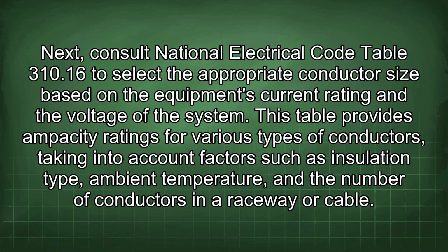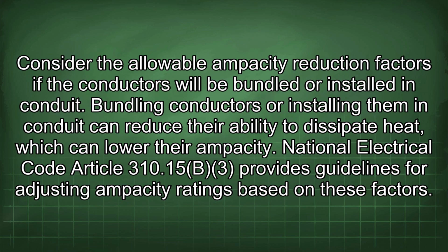Next, consult National Electrical Code Table 310.16 to select the appropriate conductor size based on the equipment's current rating and the voltage of the system. This table provides ampacity ratings for various types of conductors, taking into account factors such as insulation type, ambient temperature, and the number of conductors in a raceway or cable. Consider the allowable ampacity reduction factors if the conductors will be bundled or installed in conduit. Bundling conductors or installing them in conduit can reduce their ability to dissipate heat, which can lower their ampacity. National Electrical Code Article 310.15(B)(3) provides guidelines for adjusting ampacity ratings based on these factors.